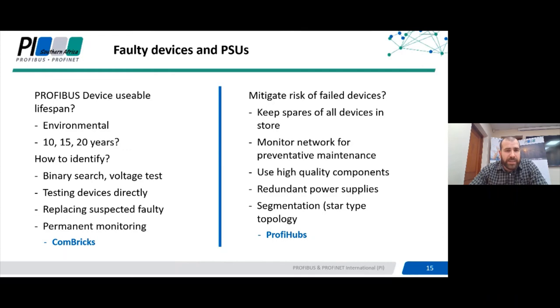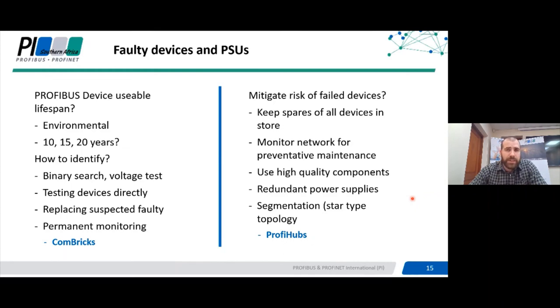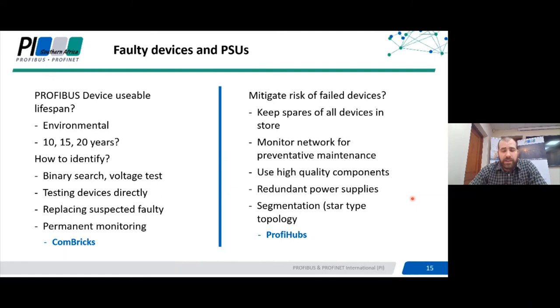Power supply issues are surprisingly a very common cause of bus failures. On inspection of intermittent comms failures or dead communications, I'll often notice the power supply is putting out less than the required voltage or no voltage at all. When doing audits I check the voltage of power supplies for good operation. I'd also recommend using separate power supplies for your Profibus communication cards — your head stations — and another for your I/O such as digital outputs and relay outputs, because relays energizing may draw excess current and create intermittent Profibus issues if on the same supply. Consider redundant power supplies using diodes or components that accept two power supply inputs and automatically switch over if one fails.